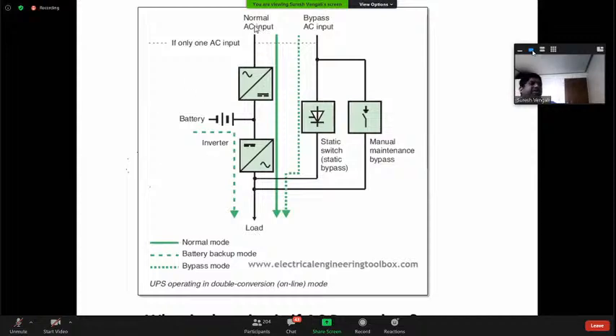So now, what is a normal input, bypass input, and battery source? You have almost 4 ways you can supply your load. One is your normal load, normal input - this way. If you lose the AC input, you have the opportunity of bypass input. And if you even lose the bypass input, you have a battery source through this line.